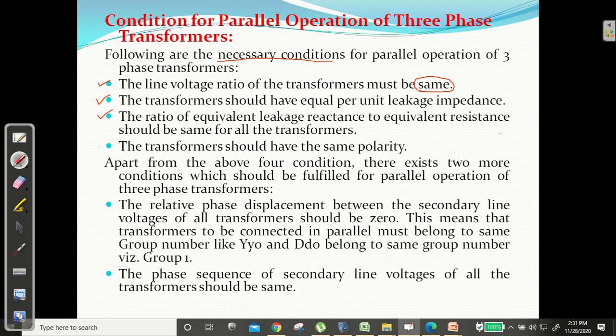Fourth condition: the transformers should have the same polarity. If polarity is reversed or different, what will happen? A dead short circuit - even at no load you get a dead short circuit, the transformer will be fully loaded, and the transformer may burn out due to short circuit. So this last condition is very, very important.